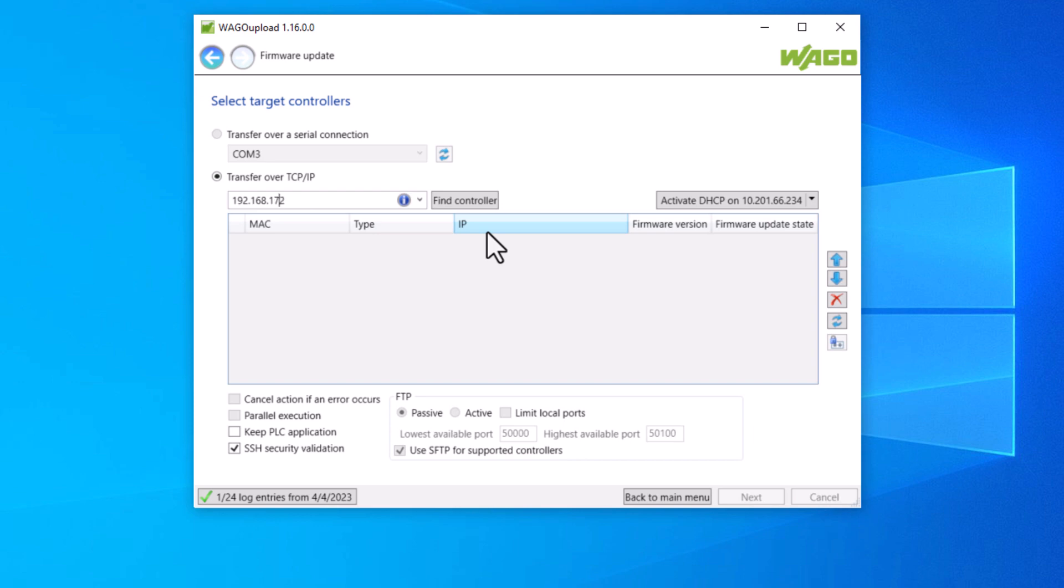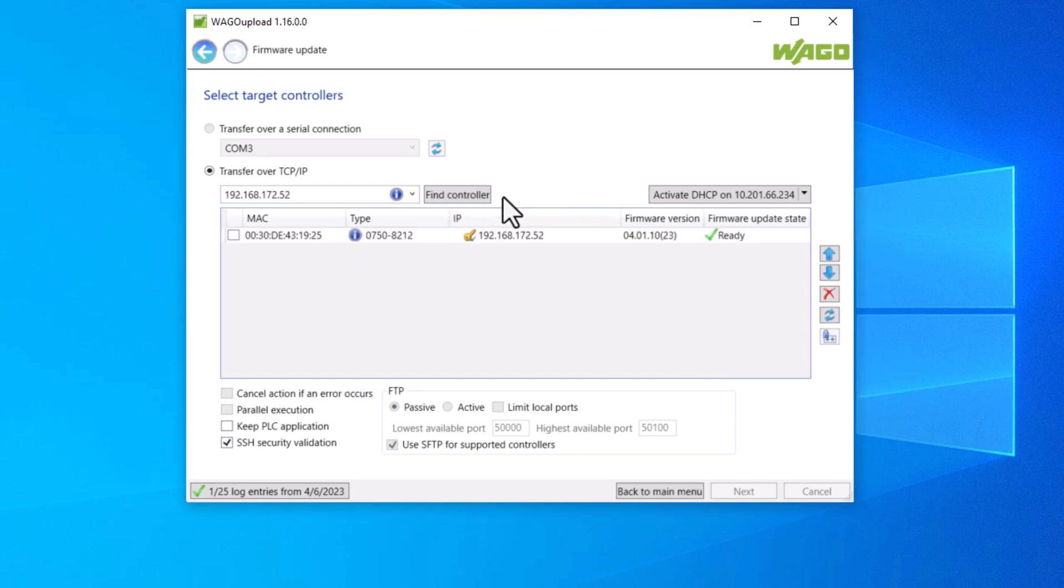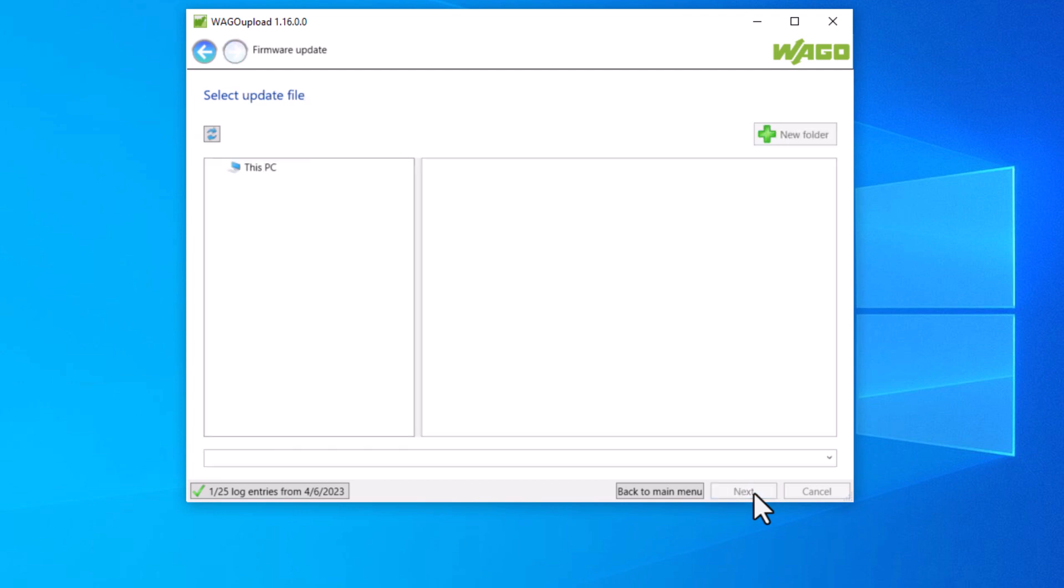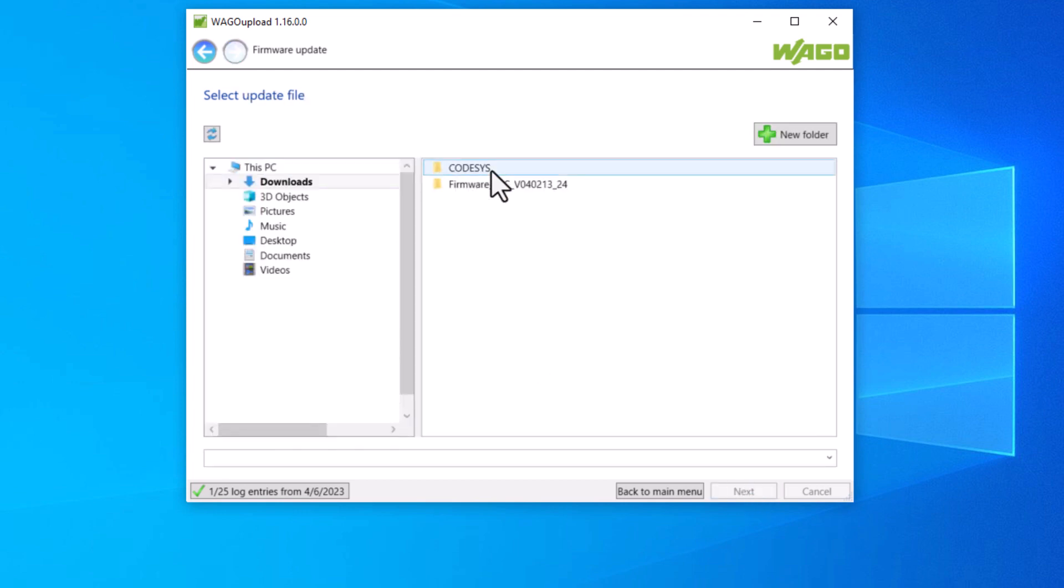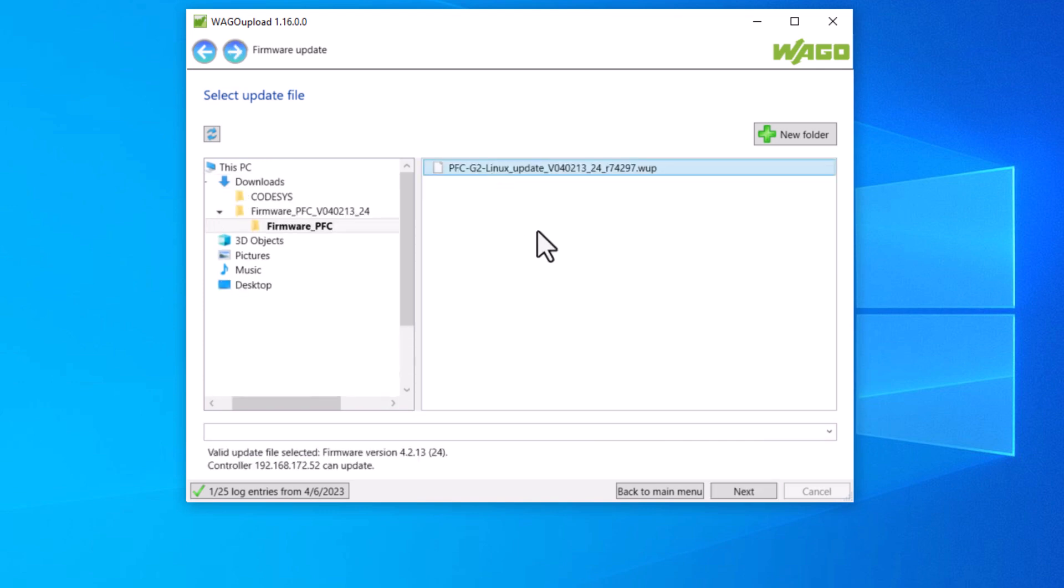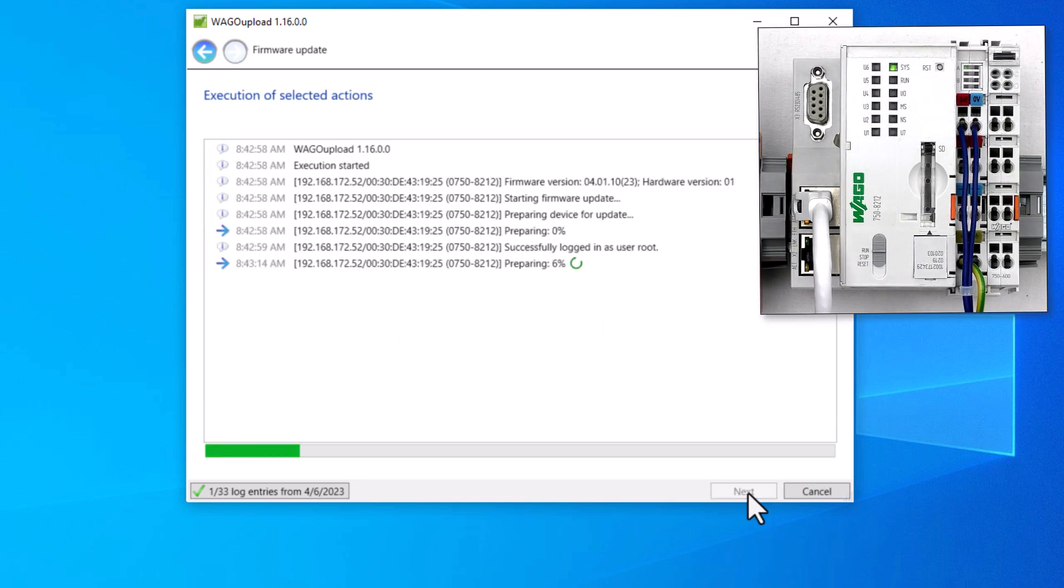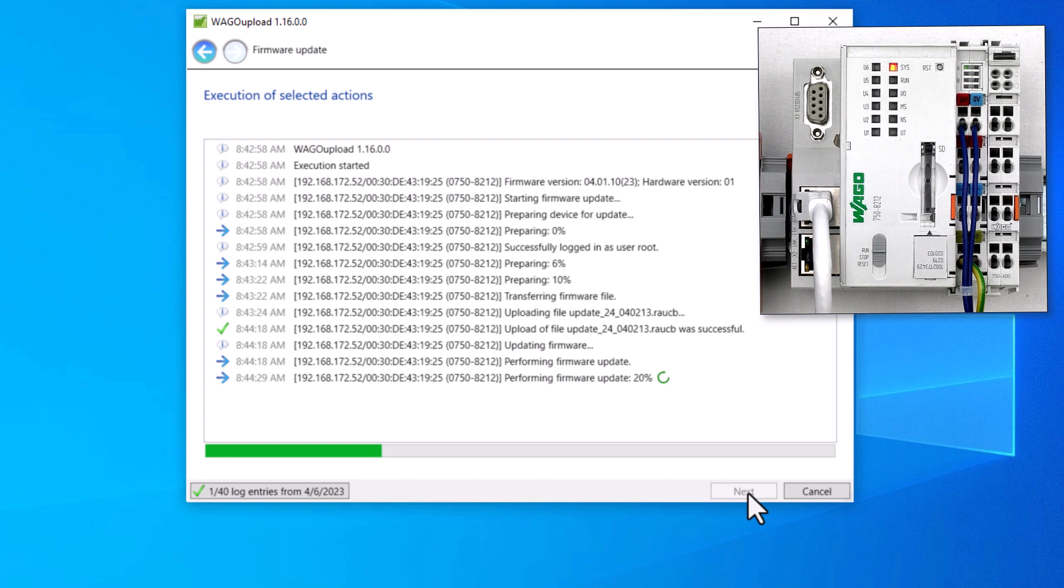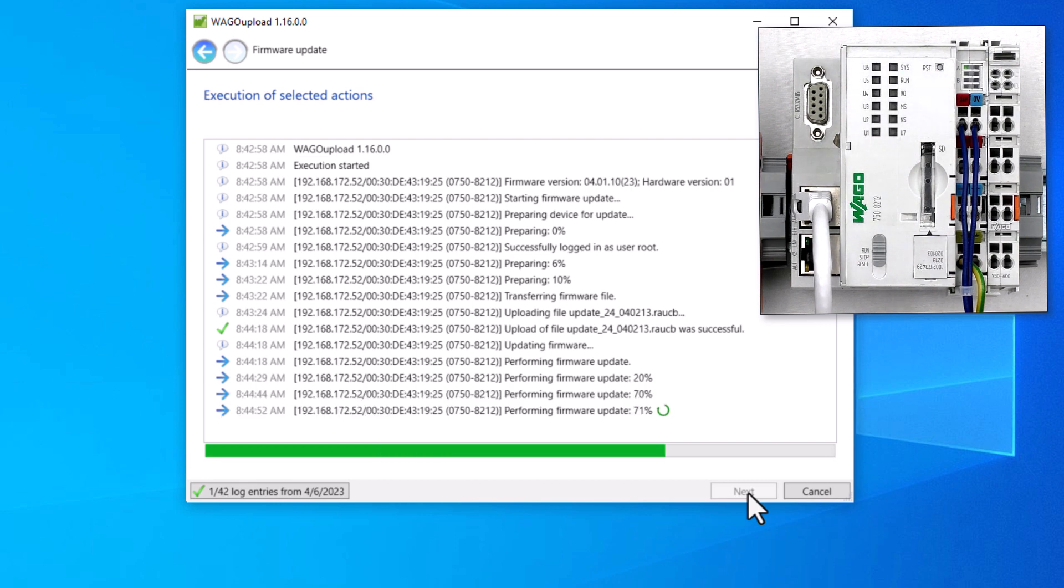Now we enter the controller IP address and want to find the controller. Our controller is displayed. The current firmware version is 23. We tick on the controller and continue. File Explorer opens, we select the previous downloaded and extracted firmware 24. Confirm with next and follow the installation dialog until firmware 24 is installed.